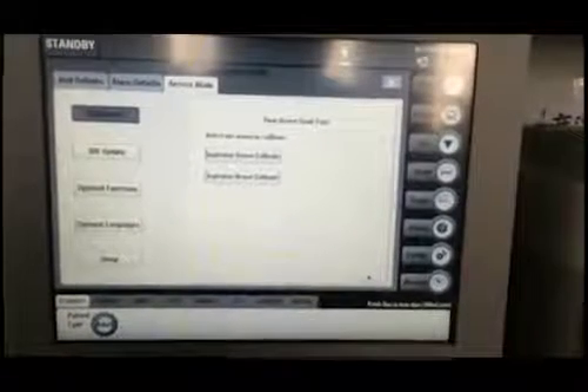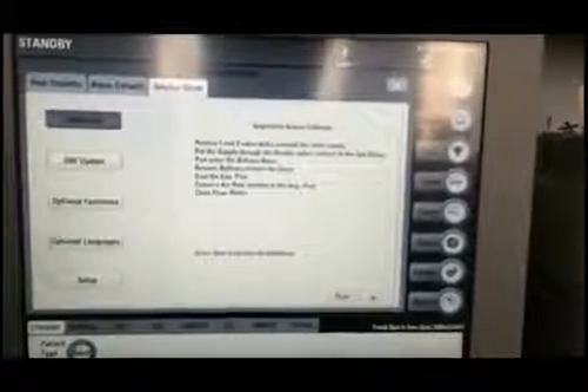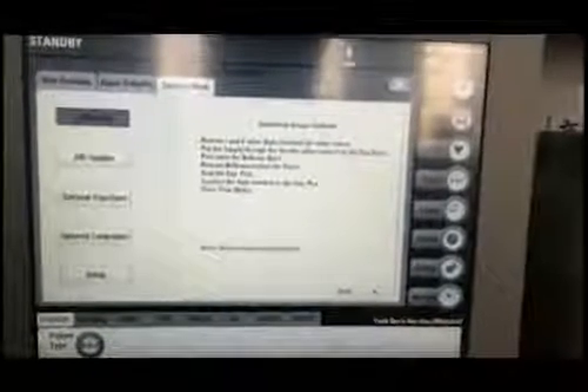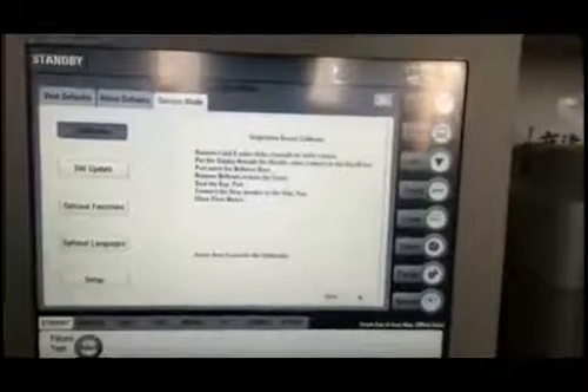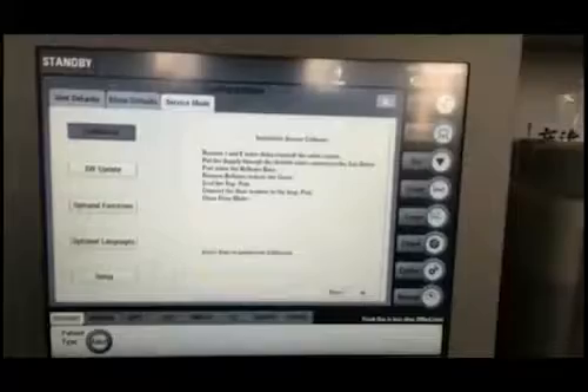There are two kinds of calibration that need to be performed. One is the inspiration sensor calibration and one is the expiration sensor calibration. The first step is to perform the inspiration sensor calibration. Please press the inspiration sensor calibration key. Please read the instructions. The first step is to remove the inspiration and expiration valve discs and reinstall the valve covers.